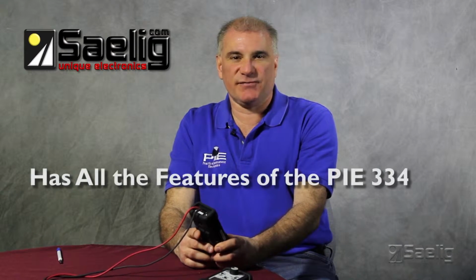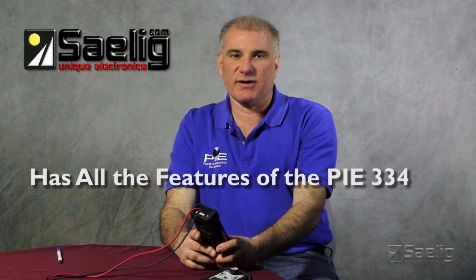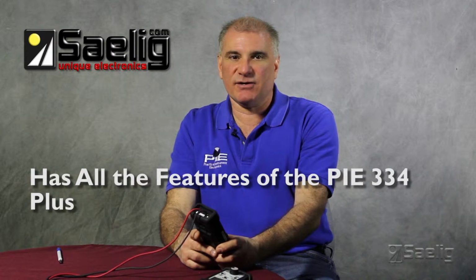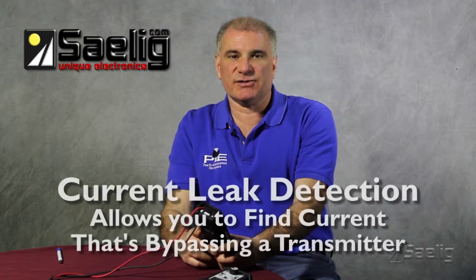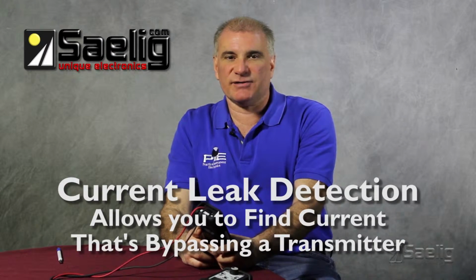The next calibrator in this line is our PIE 334 Plus. The PIE 334 Plus has all the same features as the PIE 334, including our patented current leak detection. Current leak detection allows the technician to find current that's bypassing a transmitter. It can be due to problems such as moisture, corrosion, or ground faults.